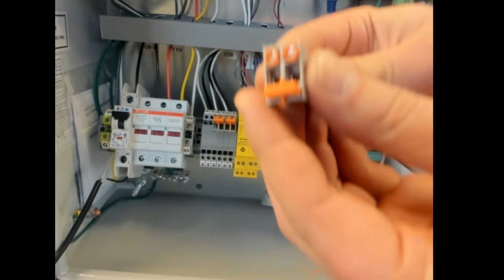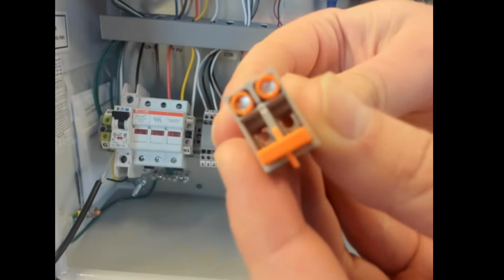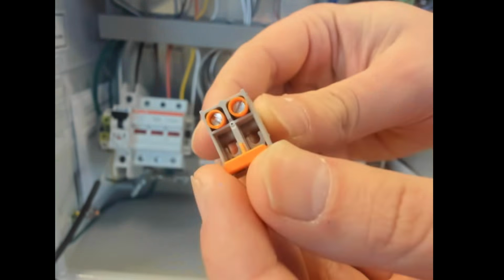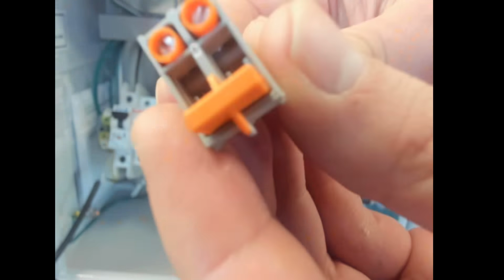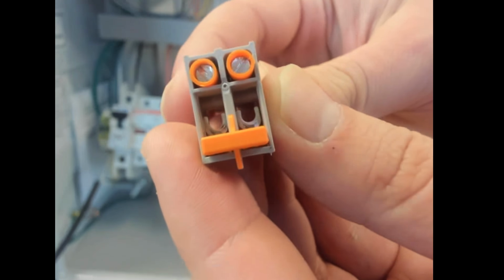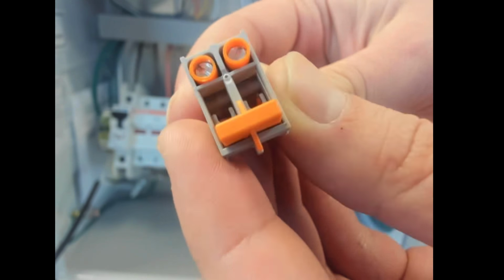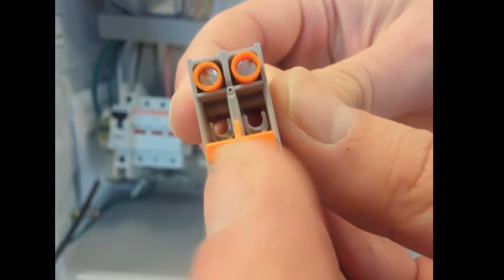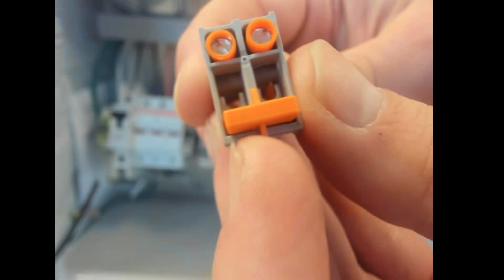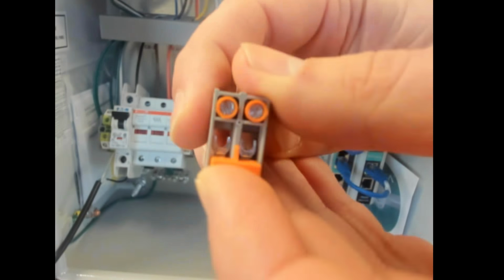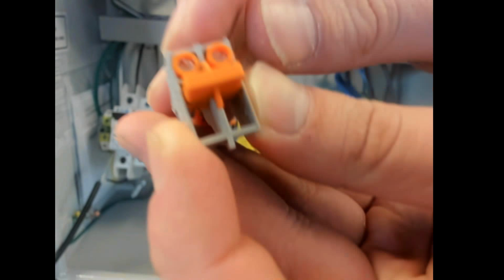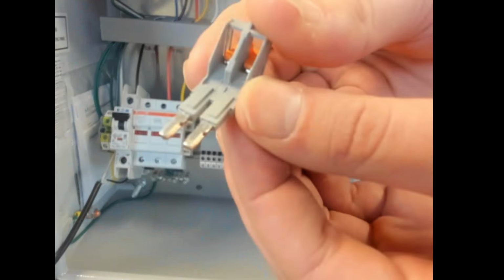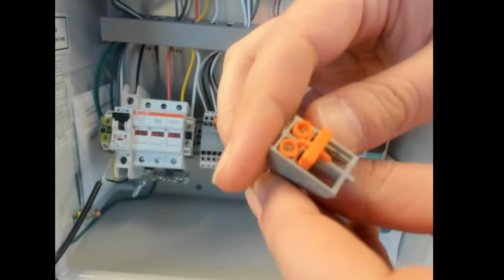These actually pull out, so I can show you a little bit more closely. The very first thing you want to notice is there are 2 screws, and then there's this kind of orange bar here. If you look really closely inside, you'll see that there's these 2 metal prongs. Those 2 metal prongs don't go to anything right now. The orange tab connects the 2 of them, but they're not actually connected to anything electrically. Now, if I were to push this up, and these screws can actually screw down to make sure that that's fastened, anything that's flowing between these 2 prongs is now electrically connected.